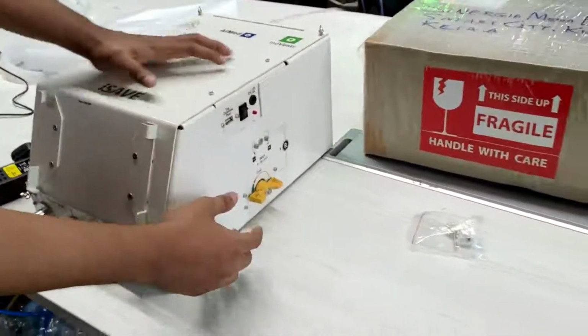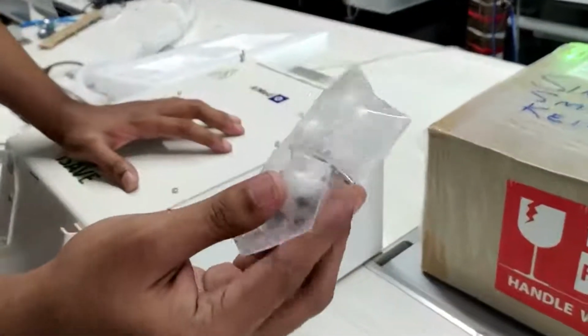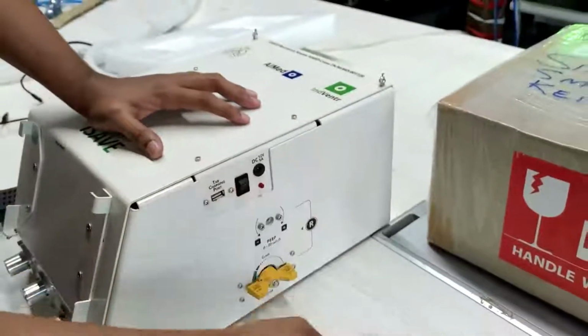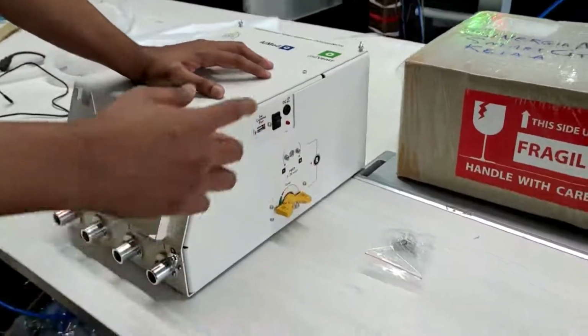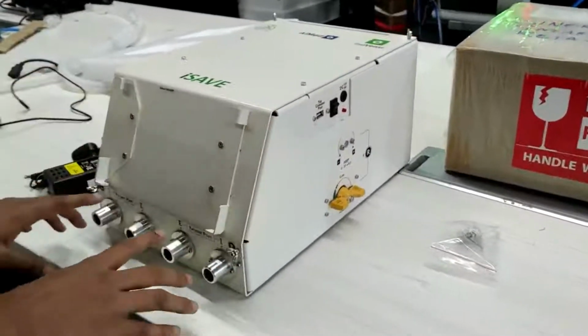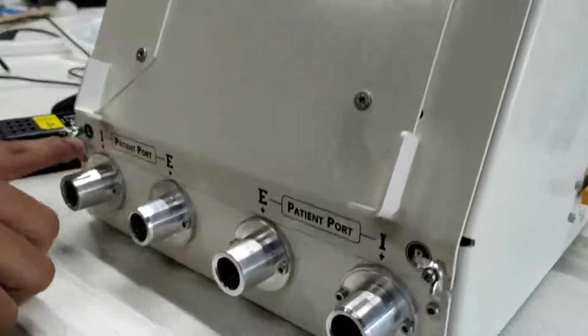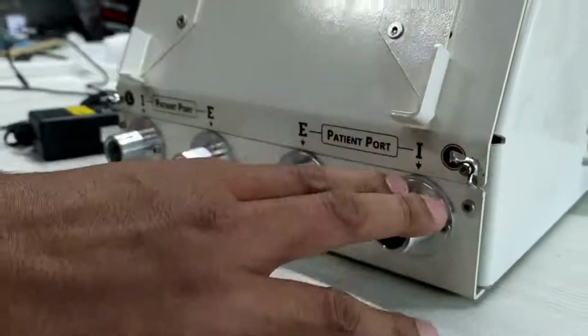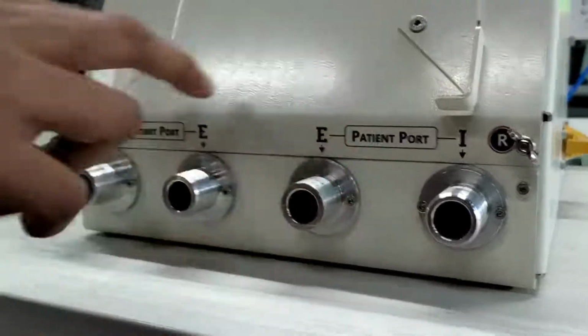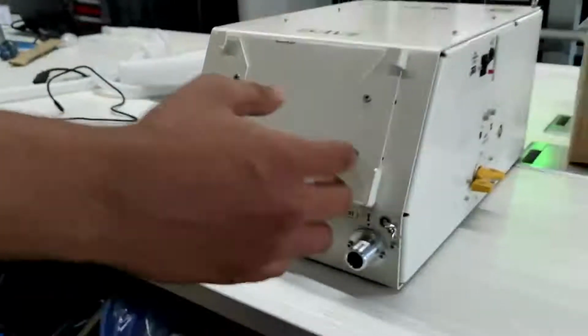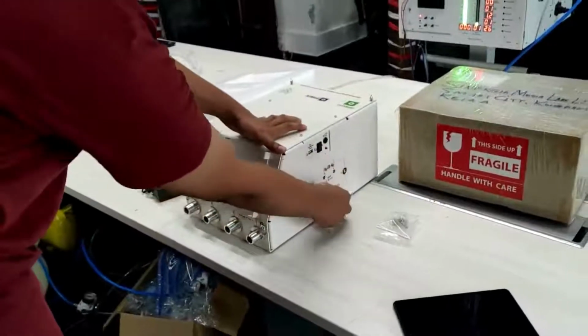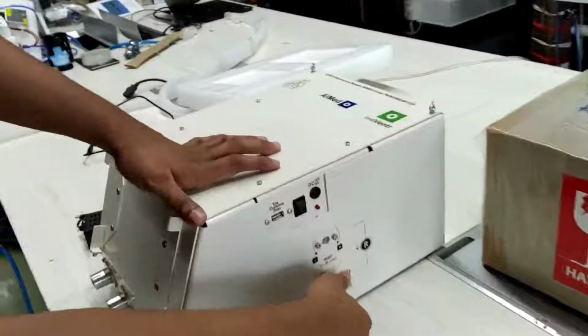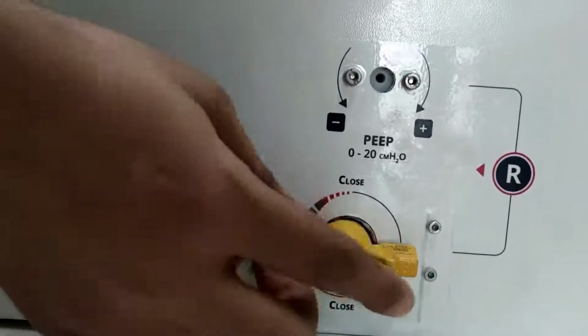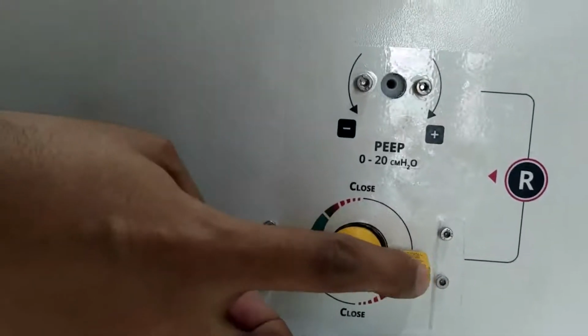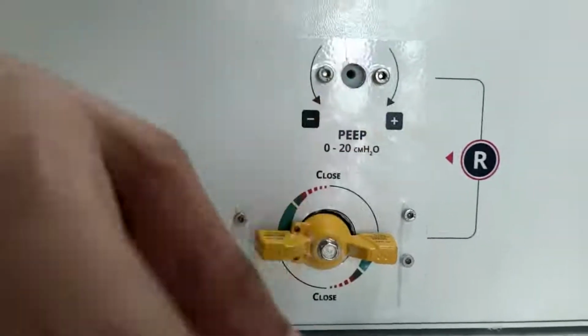So on each side we also have 2 additional components here for the PEEP, so we can adjust the PEEP. So on either side, you can see that there's patient ports. There's patient left, and then there's patient right. This is the inspiratory port, expiratory port of patient right, inspiratory, expiratory of patient left. And on the right side, you can see that there's a valve. So you can rotate this as per what you need, and basically you can control the flow that is going to a patient. Over here we got the PEEP.